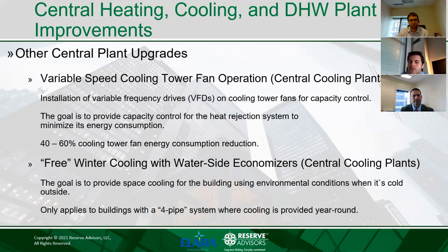These types of projects typically result in 40 to 60% energy reduction on the cooling tower fan, which is very significant. The second consideration for central cooling plants is installation of water-side economizers for what we call free winter cooling if air conditioning is required during winter time. This doesn't apply to all building types, but some buildings, usually higher-end buildings historically, are designed with what we call a four-pipe distribution system, which means that both hot water and chilled water are available at the same time for space conditioning. These buildings typically are designed to provide air conditioning even during winter time as well. Year-round cooling is available in these types of buildings.